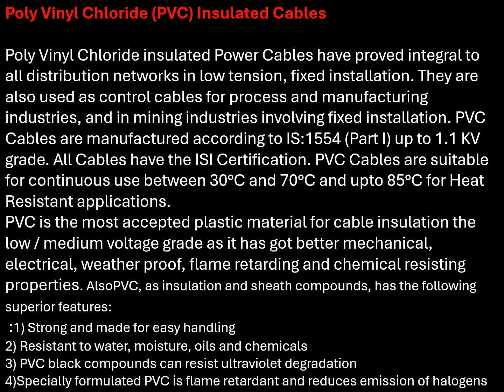Friends, the most used category of cable is polyvinyl chloride, PVC insulated cables. They have proved integral to all distribution networks in low tension fixed installation. They are also used as control cable for process and manufacturing industries and in mining industries involving fixed installation. PVC cables are manufactured according to Indian Standard 1554 part 1, used up to 1.1 kV grade. All cables have ISI certification.